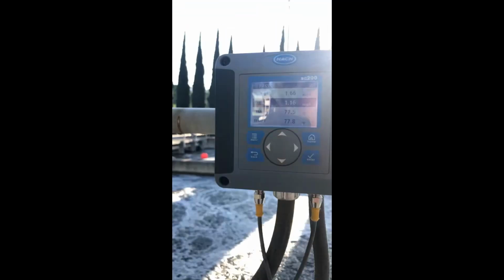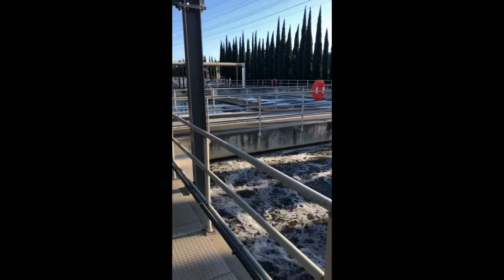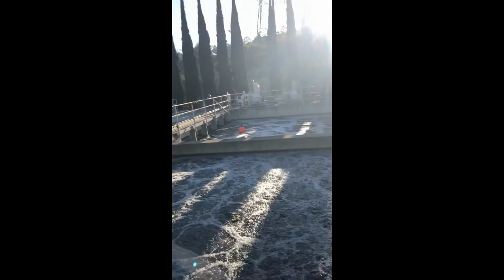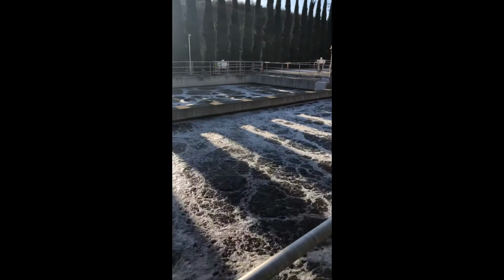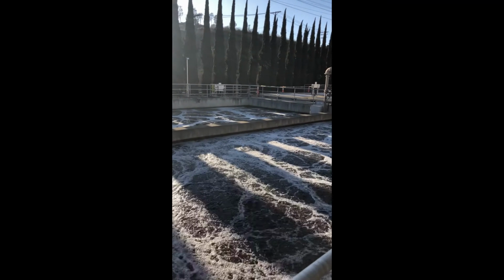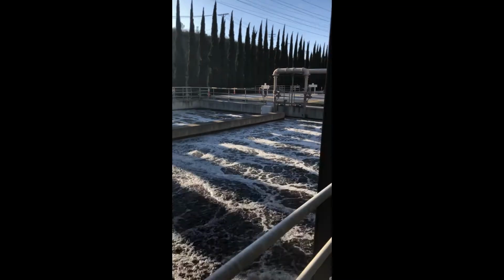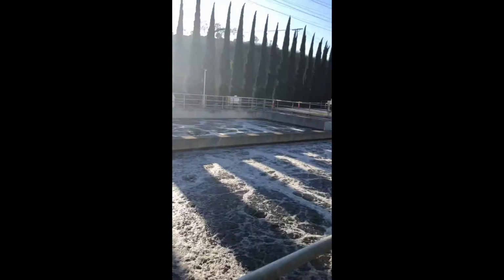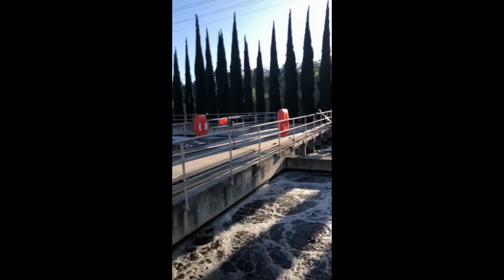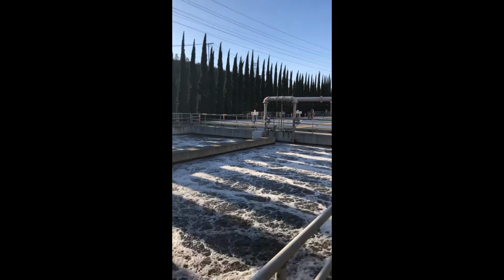And you'll see it'll make more sense when we look at the SCADA control screen. With the operators, they can put in a set point of how much dissolved oxygen they want these tanks to always have. That will measure the result compared to the set point and operate those control valves.